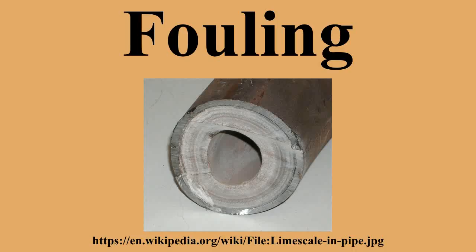Progress of fouling with time. Deposit on a surface does not always develop steadily with time. The following fouling scenarios can be distinguished, depending on the nature of the system and the local thermohydraulic conditions at the surface. Induction period. Sometimes, an initial low fouling rate is observed when the surface is new or very clean. This is often observed in biofouling and precipitation fouling. After the induction period, the fouling rate increases.